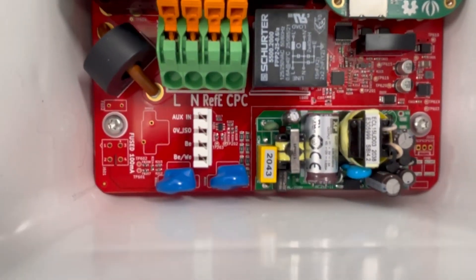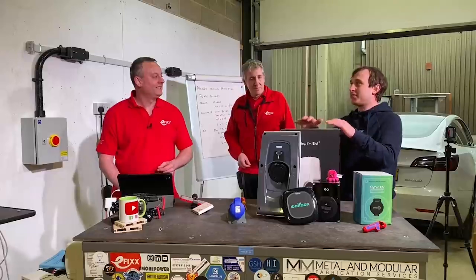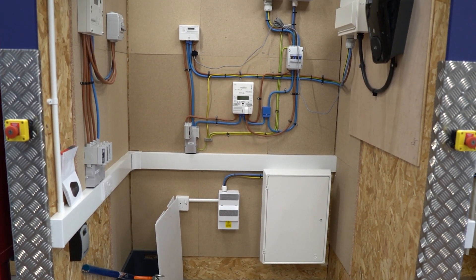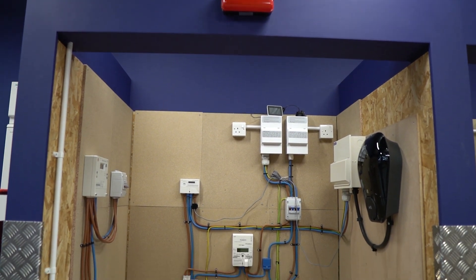A lot of the other PCB equipment is for general safety. Here in the UK there are quite a lot of rules — it may include RCD protection, and DC leakage protection, which is important because electric cars can leak some DC current down your power lines. I did a video with eFix about why you shouldn't use a granny cable, since most granny cables don't have that protection. There's also PEN fault detection — if your earth comes from the main grid and isn't your own system, a PEN fault could mean touching a metal object in your house gives you an electric shock.